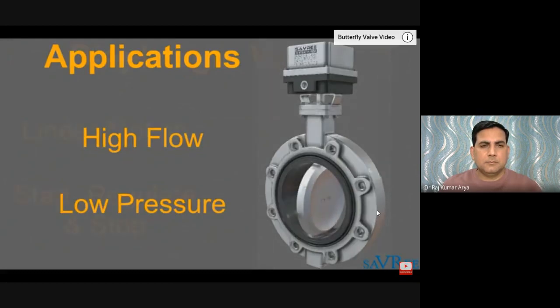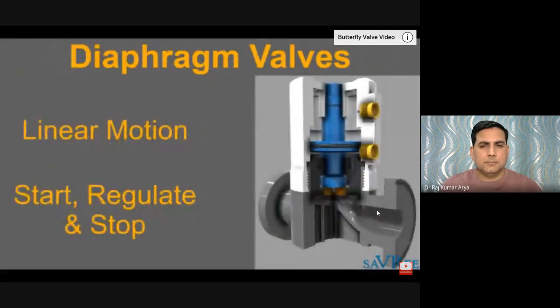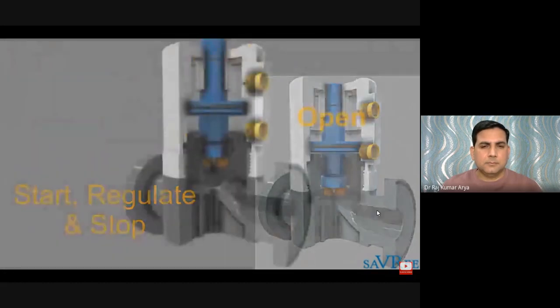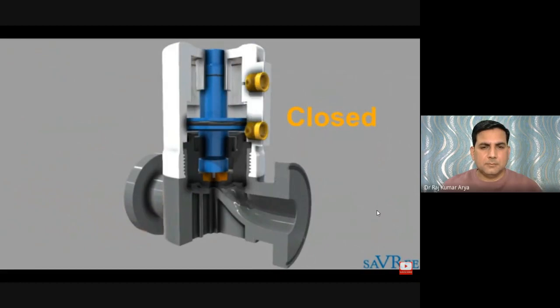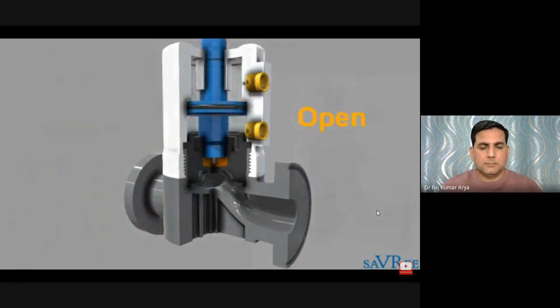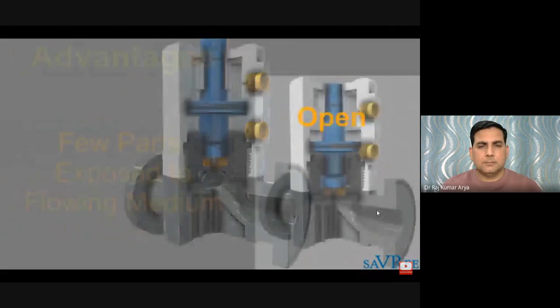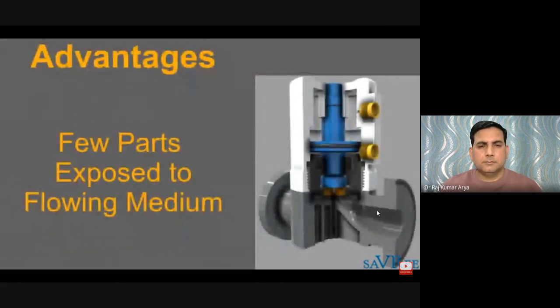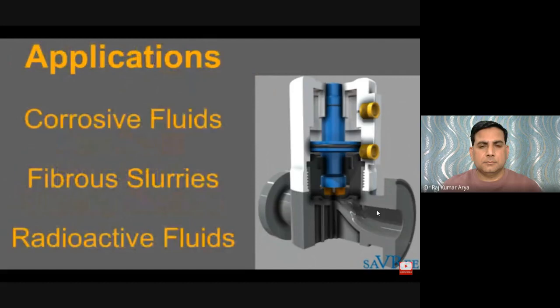A diaphragm valve is a linear motion valve used to start, regulate, or stop fluid flow. A flexible diaphragm can be raised or lowered onto the valve seat to open or close the valve. A great advantage is that very few parts are exposed to the flowing medium — only the flexible diaphragm and internal flow passages are exposed. This makes it particularly well suited for handling corrosive fluids, fibrous slurries, radioactive fluids, or fluids that must remain free from contamination.